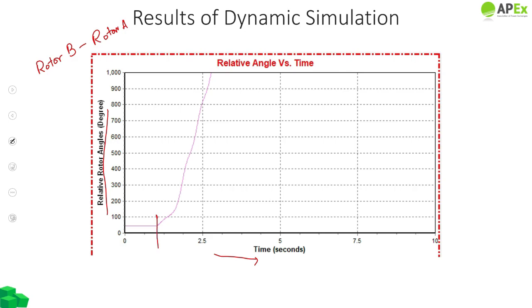Before the occurrence of the fault, we had a relative rotor angle of less than 50 degrees. It means that the system was working smoothly and in sync. Both generators were perfectly synchronized. But when the fault occurred, our rotor angle continued on an increasing trend, and at this point the relative angle crossed the threshold of 90 degrees. As we said before, once the relative angle crosses 90 degrees, the generators lose their synchronism. And the same is shown in the plot.